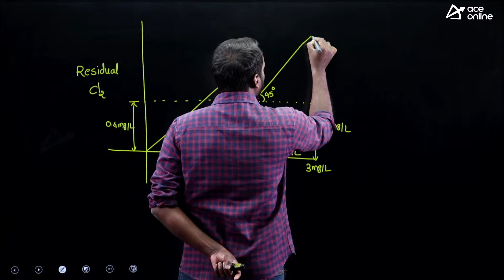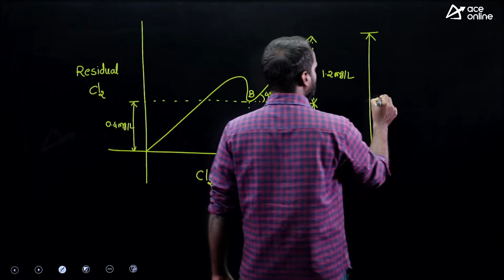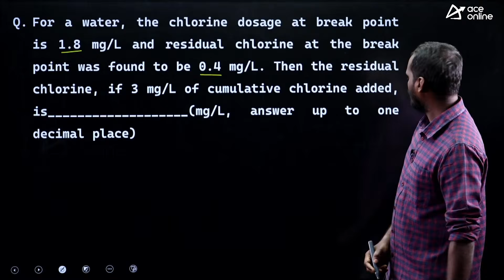But he is asking after a cumulative dose of 3 milligram per liter, what is the total residual chlorine? This is the total residual chlorine, right? 1.2 plus 0.4 is 1.6 milligram per liter. This is the total, right? The answer is, you need to enter 1.6 milligram per liter. Answer up to 1 decimal place. You are getting 1.6 exactly. In these kinds of answers, you are nowhere getting decimal values, right? Exactly you are getting 1.2, 0.4, 1.6. They'll give 1.6 as your answer. They don't give any range, since you are getting the answer exactly, right? Be careful with this numerical answer type. Okay.